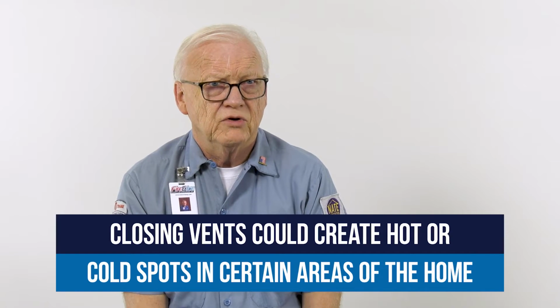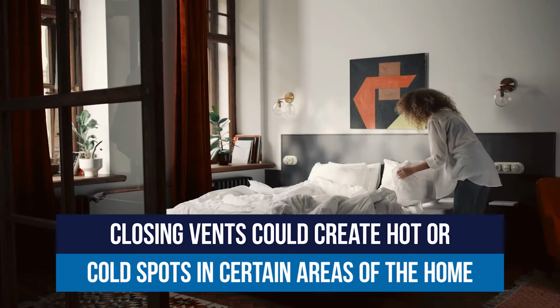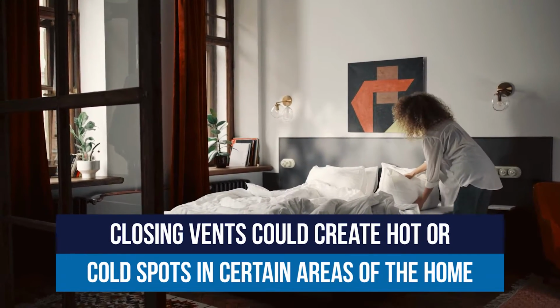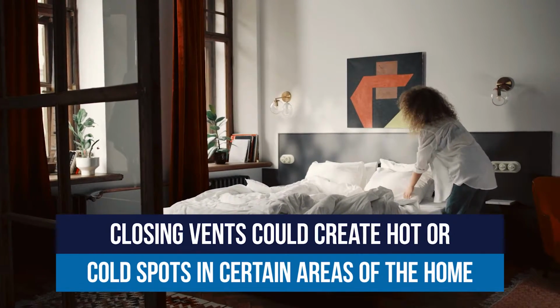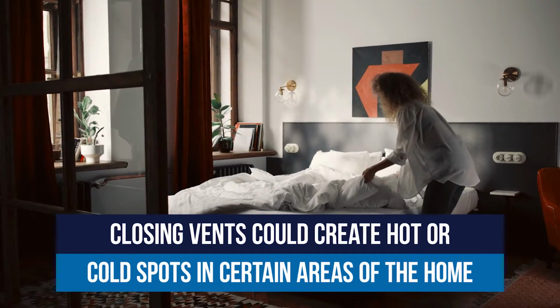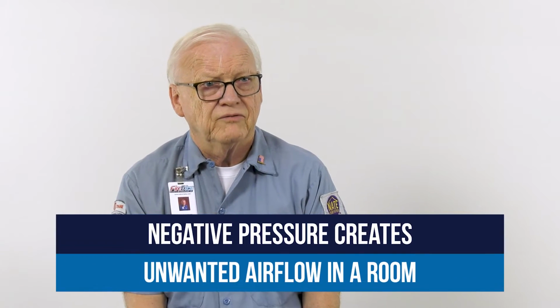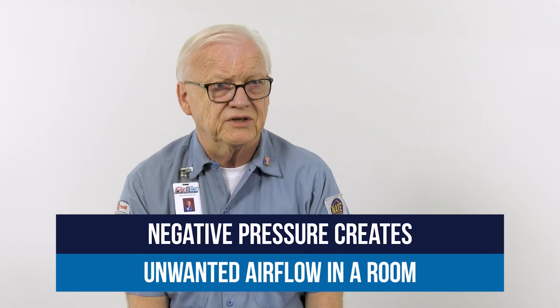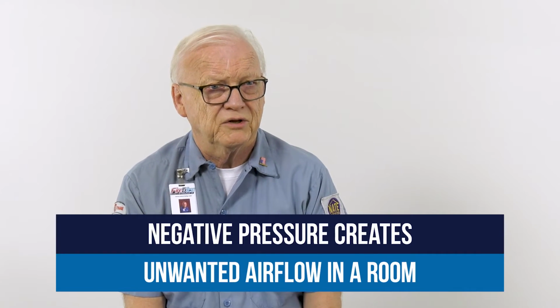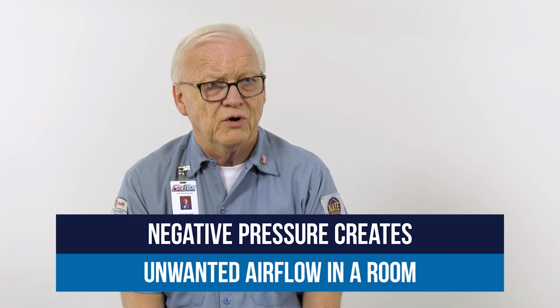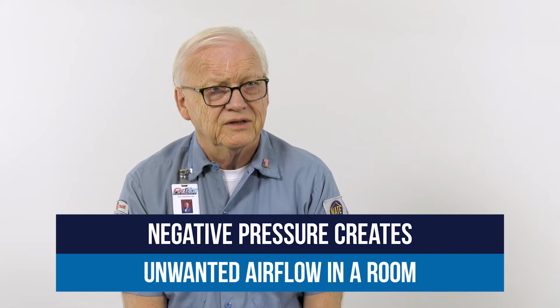But if we close a vent in a particular room, say a bedroom, and we have a return air in there as well, we're not pressurizing that room, so the return actually puts a negative pressure on the room. And when you have negative pressure in a room, air is going to flow in through the ceilings or the windows to bring in cold or hot air. So it's not always a good idea to close the registers all the way in a room.